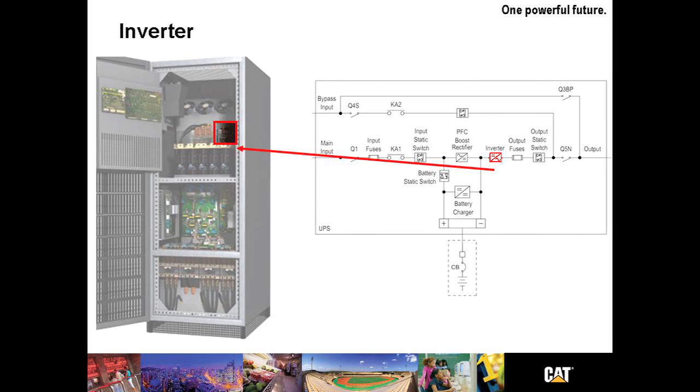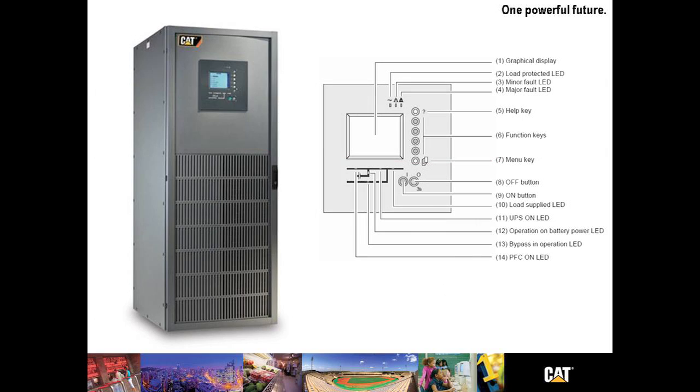The inverter operates at a variable chopping frequency of approximately 5 kHz. During steady state, the output voltage will be held to within plus or minus 1% of the RMS values of the phase-to-phase voltage. During an overload situation, the load is immediately transferred to bypass, assuming of course the bypass is within tolerance. During a transient event from the load, the UPS will handle 100% step loads with no more than 2% voltage change in RMS values phase-to-phase. Transient response to within 1% plus or minus range of the RMS value is less than 100 milliseconds.